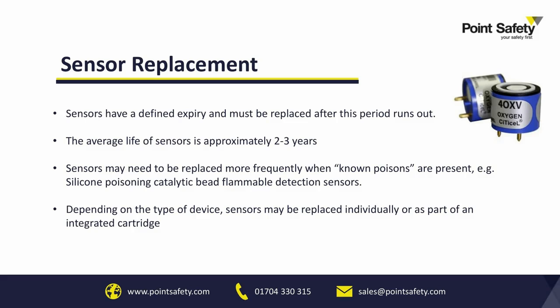Depending on the type of device, sensors may be replaced individually or as part of an integrated cartridge. We're seeing more nowadays that they are individual sensors, but in the past there has been a number of meters with cartridge variants that have 2, 3 or 4 sensors within that cartridge, and you replace them all together at the same time.